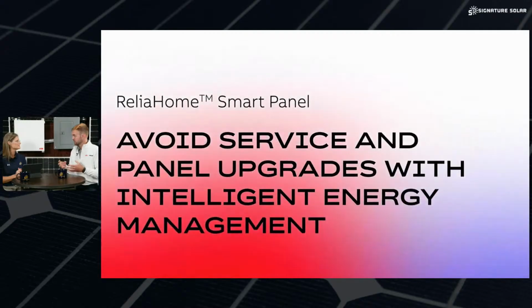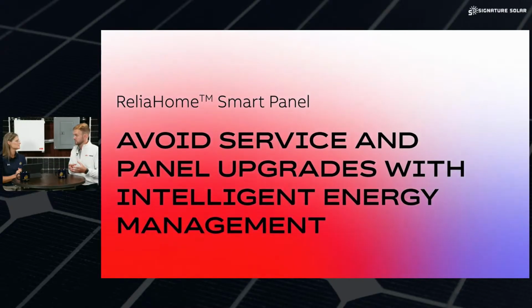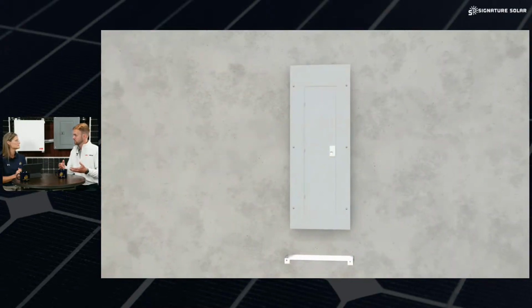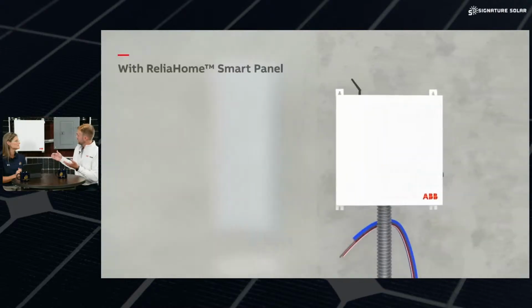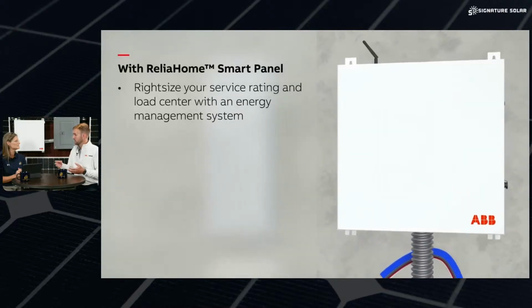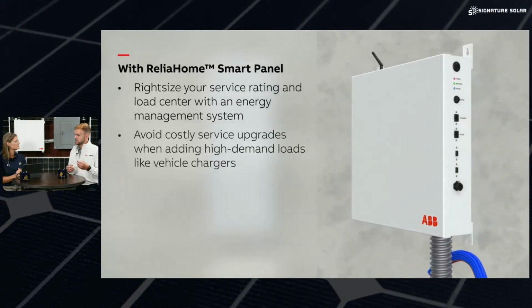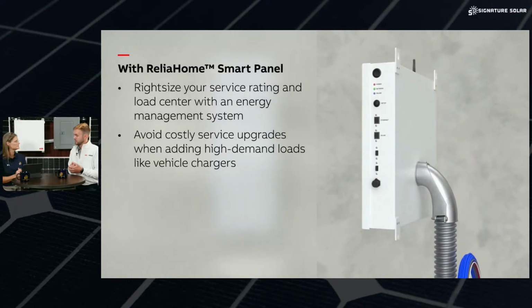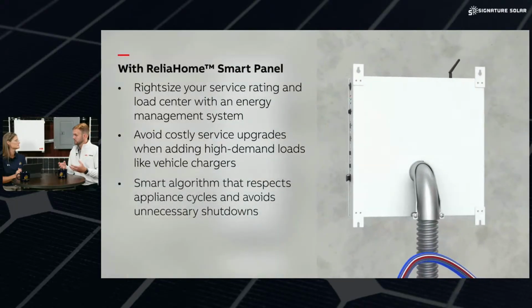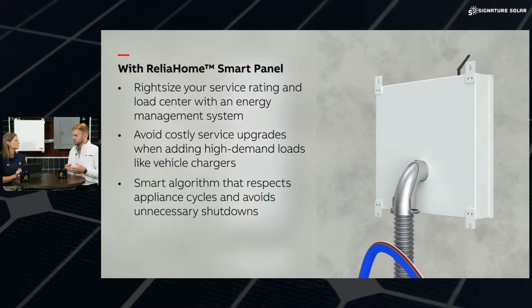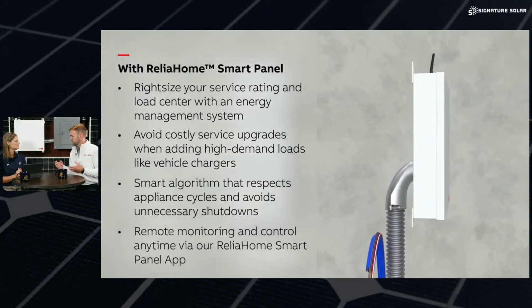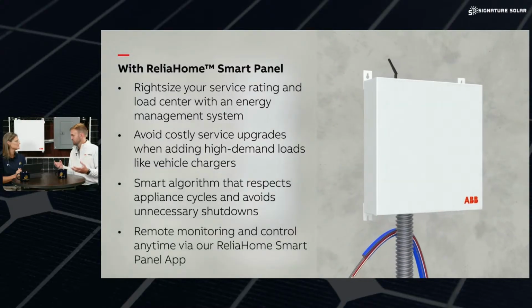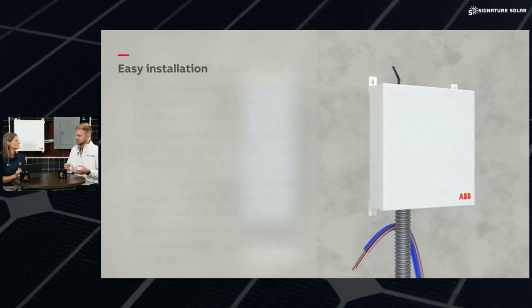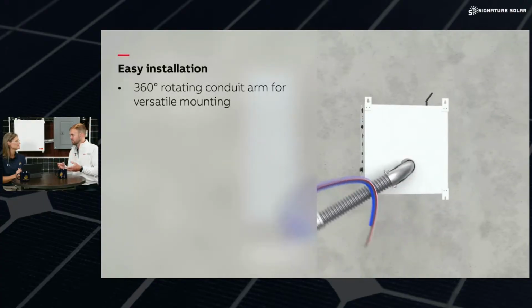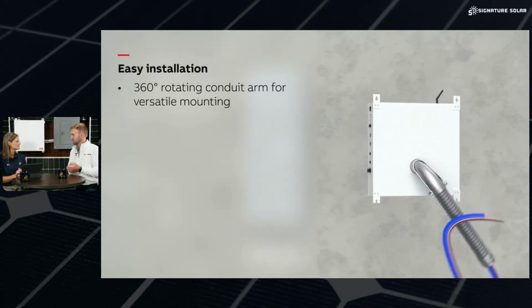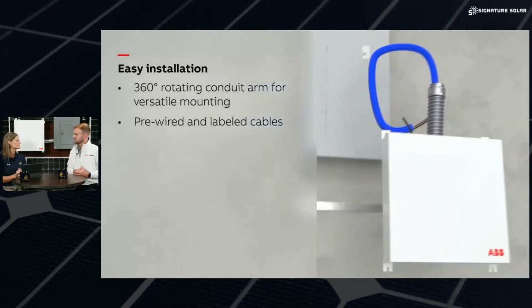We take the approach of controlling what matters, so we want to connect to the largest circuits in any distribution panel. In the box we have 6 lines rated up to 60 amp and 6 lines rated up to 30 amps. By connecting to those 12 line sets, we're oftentimes controlling upwards of 80% of your energy consumption. Kind of the 80-20 rule, right? 80% of your consumption by connecting to maybe 20%, or even sometimes fewer, of your circuits, to get the most value out of the system.